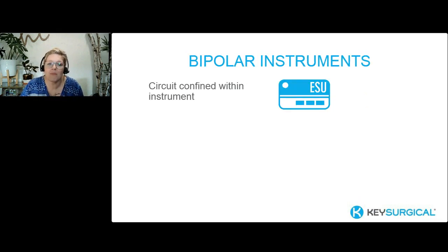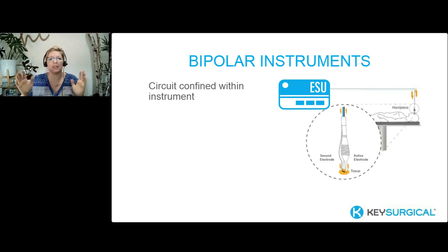So first, when we talk about bipolar instruments, this is what we have when we have the circuit contained within the instrument itself. So if we remember that circle, we have the ESU that's creating our voltage. We apply the current with the active electrode, and it returns really at that same spot. As you can see, that's how we're creating a closed circuit, is using the device. That's why for bipolar instruments, we don't have to use a Bovie pad. A dispersive pad is another word for those.